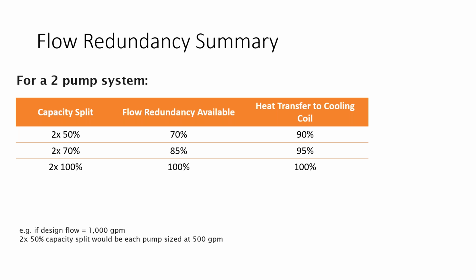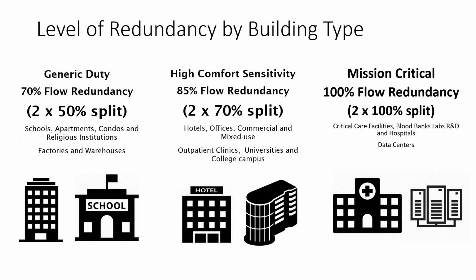So now also when we bump up our capacity to 70%, so that's by enlarging the Tango to the next size, we'll get an 85% flow redundancy per pump, and that gives us 95% of heat transfer. And I'm sure we've designed way more than 5% excess capacity into our system. So we're already probably over 100% of what we actually need. And in a part load, we generally need a lot less. And then of course, 2 by 100, you're always going to have 100% flow and 100% heat transfer. So no change there. So this I thought was very interesting because the conversation comes up.